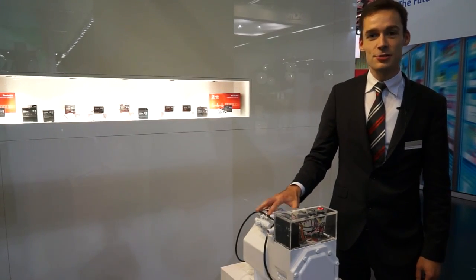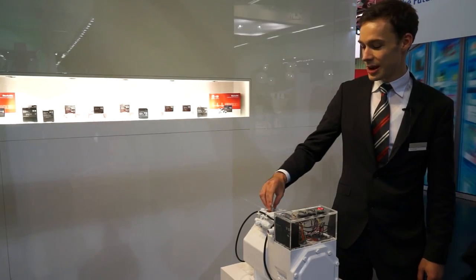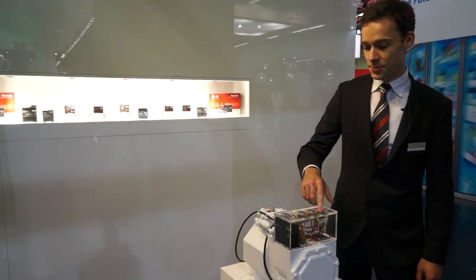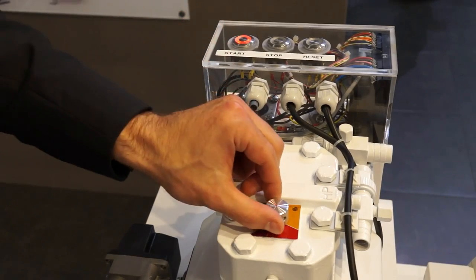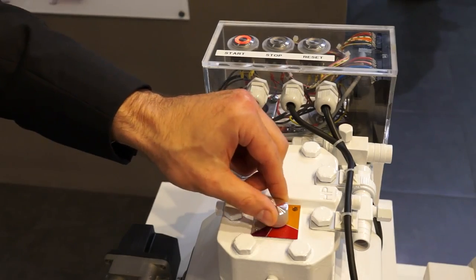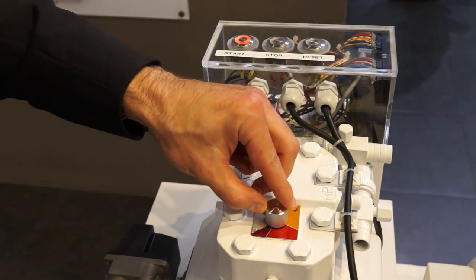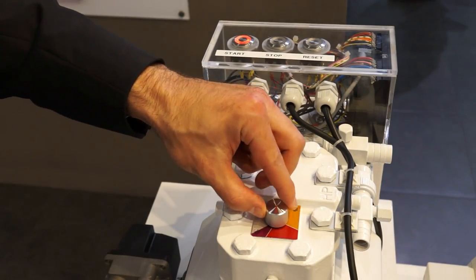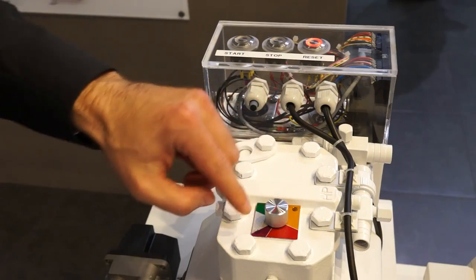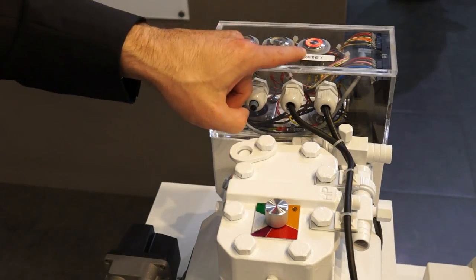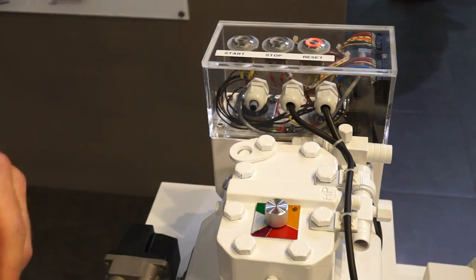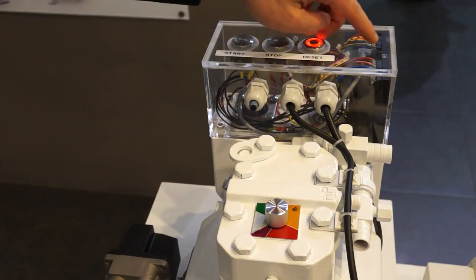We've used a potentiometer to simulate this here on a real compressor. The compressor is running. Now we simulate the temperature increasing to a critical level. The compressor is switched off and the LED shows an error.